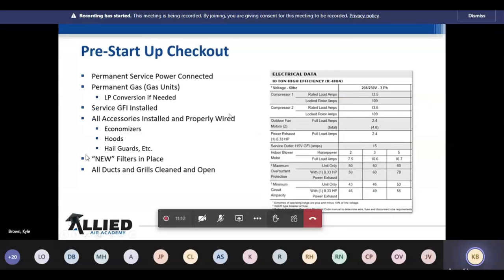So, you know, permanent service power, gas, if you need LP, if you got your conversion kits, make sure it's the right conversion kits. You want to make sure you have everything set. Now, the last two: if you're already on the roof and they've actually cranked this unit up before you or the company has had a chance to come up and make sure everything's all right, then obviously your rated load amps and everything over here is probably going to be correct. But you need to go back through and make sure all these amperages and everything are correct, so when inspectors and other folks come around, you have the right disconnect boxes and everything else.